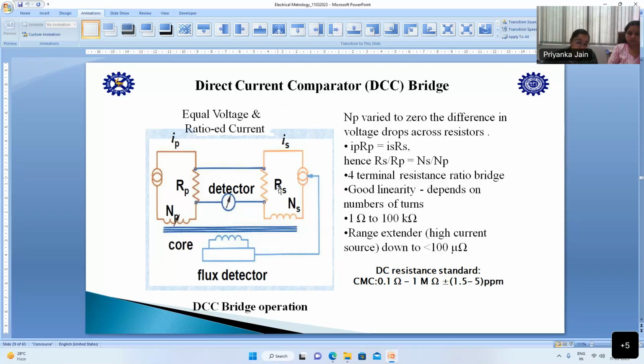Here we have a primary standard, that is, a 1 kilo ohm standard calibrated against the QHR. This we connect here, and internally there are a number of turns. Based on this resistance, these turns will be set digitally here. So based on this current and turns, the current will start flowing here. Similarly, we have another unknown resistance RP, with variable turns NP, which is unknown. Based on this current, it will start flowing another current here. So based on this number of turns it will energize, and some current will flow here.